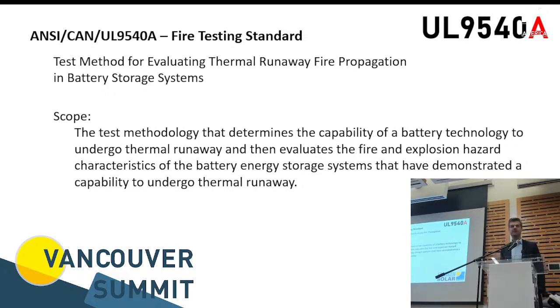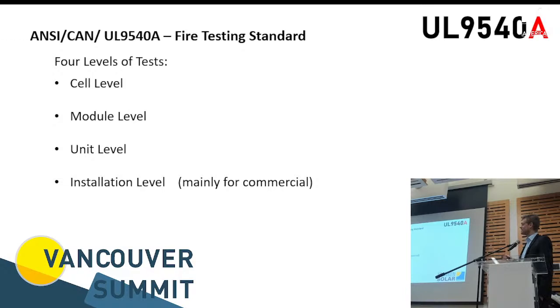That's typically the case for a lithium-ion chemistry. And evaluate what is happening to a fire and the explosion hazard options to that system when it goes under thermal runaway. The test is characterized in 4 different levels. And we have the lowest level, which is the actual cell itself. Then the next level is if you put multiple cells into a battery module. Then you can have multiple battery modules in a unit. And if you have very large-scale systems, like containerized battery storage systems, then we talk about the installation level, where pretty much all these components, including fire suppression systems and whatever, will be put into a system, and then it will be tested and inspected to that highest level in the installation itself.